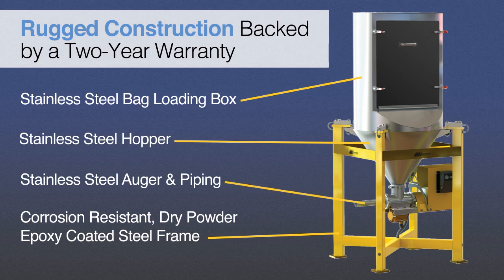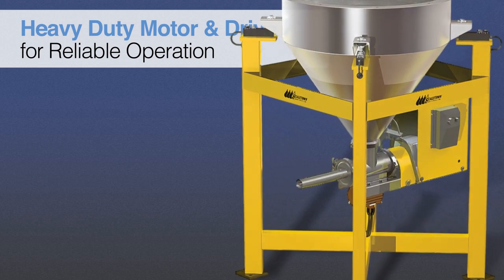The VMF28 Basic Unit employs a heavy-duty motor and direct-drive mechanism, featuring a variable-speed TENV 90-volt DC washdown gear motor with a quick-change auger assembly. Standard motors are available from one-eighth to one-quarter horsepower, while optional Washguard and explosion-proof motors are available from one-third to one horsepower.